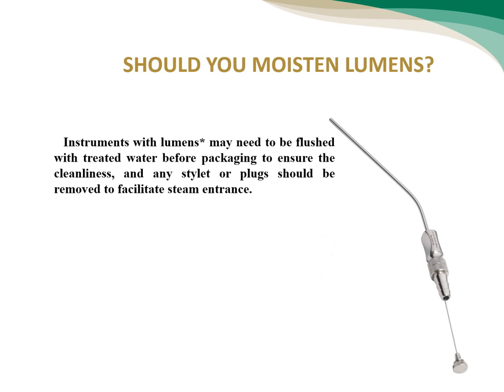Should you moisten lumens? Of course, lumens in the instrument should be flushed with treated water before packaging and dried and checked for cleanliness. Stylet and plug should be removed to facilitate the steam entrance inside the lumens.